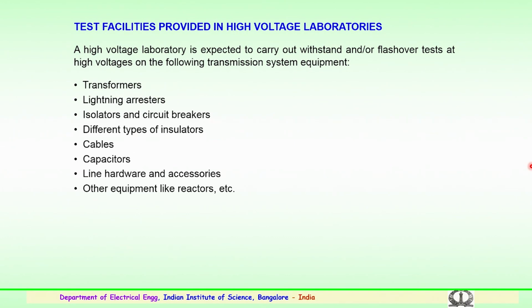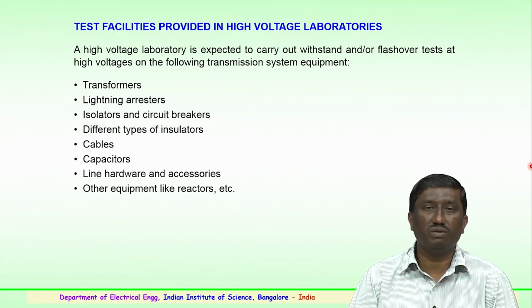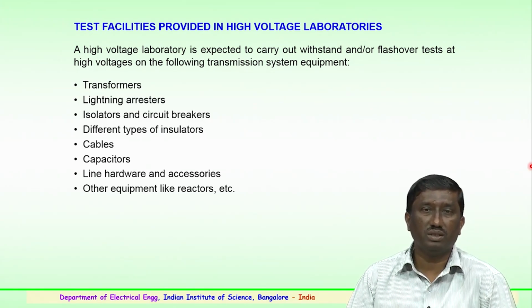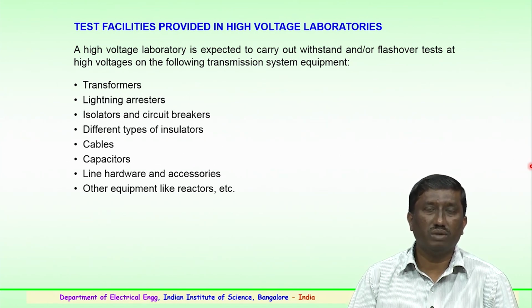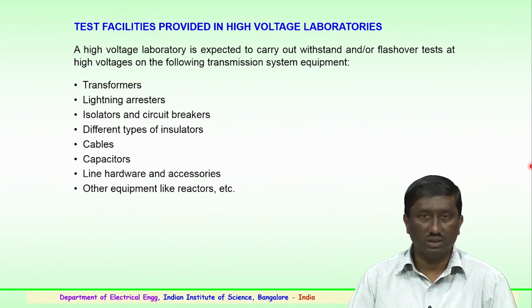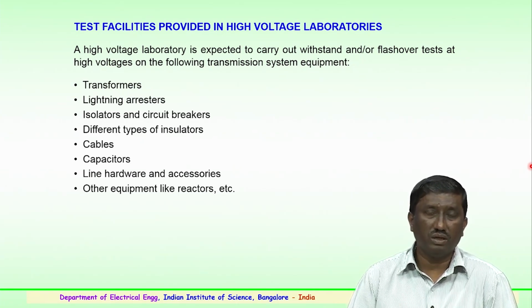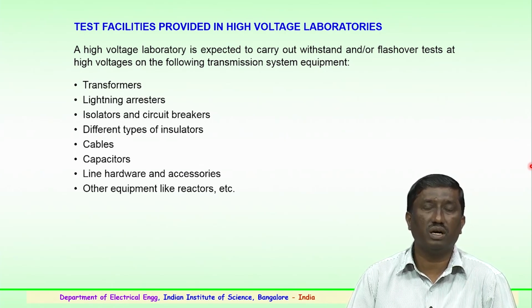Lightning arresters have to be tested for various type tests. It could be lightning impulses of 8 by 20, a switching impulse of 30 by 60 microseconds, a high current test of 4 by 10 microseconds, and a long duration test which ranges up to a few milliseconds. Apart from that, there are also the operating duty cycle tests which the lightning arrester will undergo in the laboratory, where both AC and impulse currents are impinged on the surge arrester or lightning arrester.